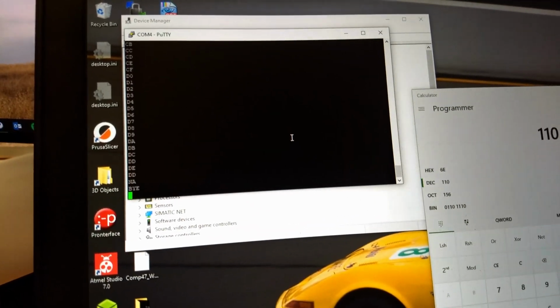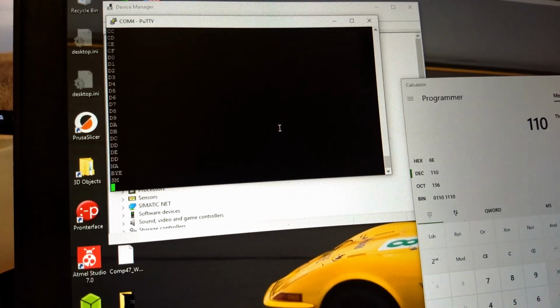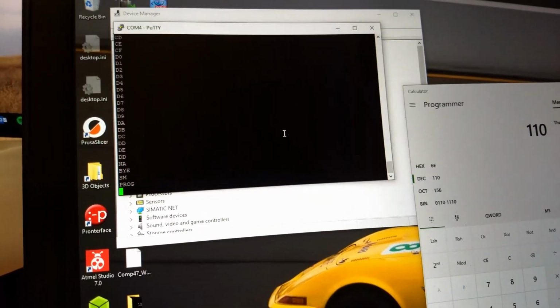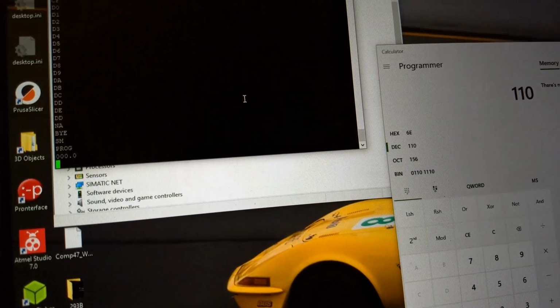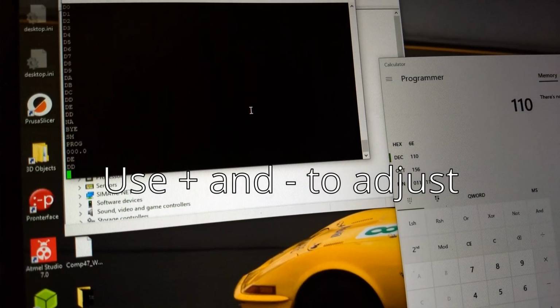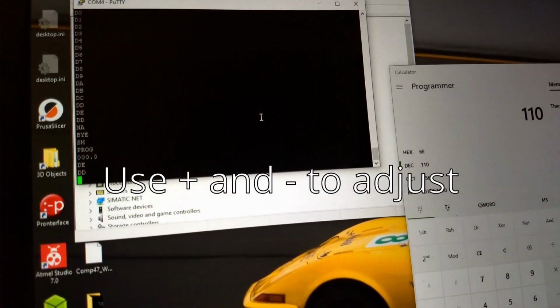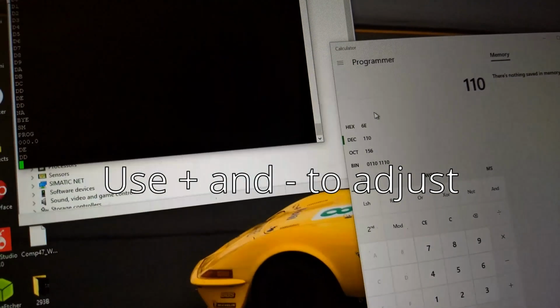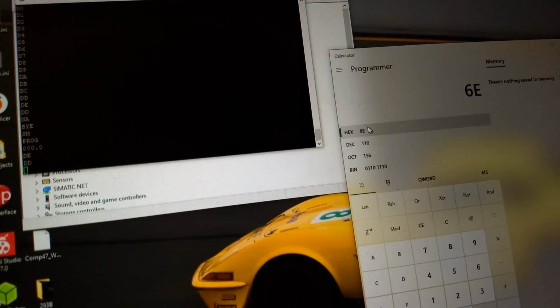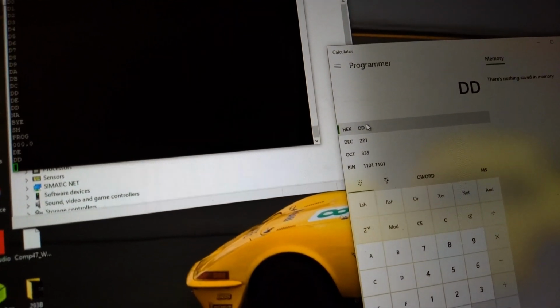And so now if we come into the smart mode, so we hit Y, gets us into smart mode, one, wait for a second, hit one again, we're in programming mode. It's P gives us our power load gain. And so if we hit it, we could see our default was DE or DD. And so that's a hexadecimal number. So if we come into here and we hit DD, so it's our current.